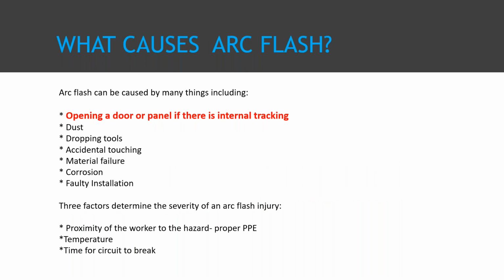So it can be caused by a lot of different things. One of the big ones that we hear in talking to companies that have had an arc flash incident is opening a door or a panel, specifically on switchgear, if there's any kind of a problem going on inside. So one of the ways we mitigate that with ultrasound is, before that panel is ever opened to do an infrared inspection, a quick ultrasound scan around the air gaps of the door can actually tell you if you've got any popping or crackling noises internally that would tell you, don't open that panel or don't open that door. To randomly open a door, whether it's for visual inspection, whether it's for infrared inspection, is crazy and can definitely be a source of an arc flash.